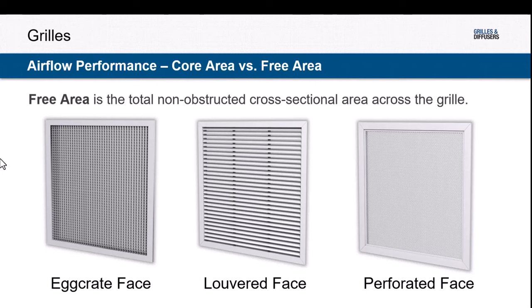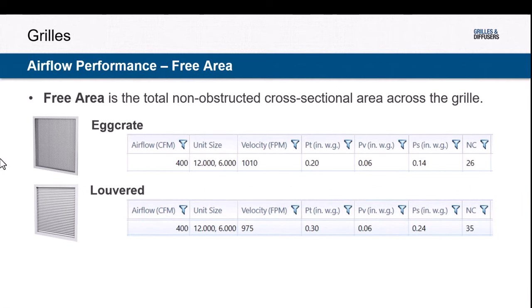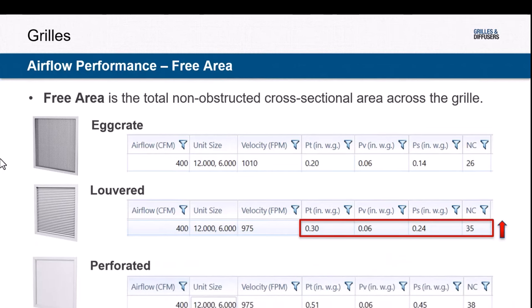The actual geometry, construction, and blade spacings — and in some cases perforated grills — have different performance associated with them because of free area. Comparing a 12x6 egg crate grill at 400 CFM versus a louvered grill at 400 CFM, pressure drop and sound both increase — sound by almost 10 dB, which would be perceived as twice as loud. A perforated grill with even smaller free area at the same conditions yields a pressure drop of about 0.45 and an NC of around 38. So the type of grill can help you achieve the performance characteristics you're looking for.